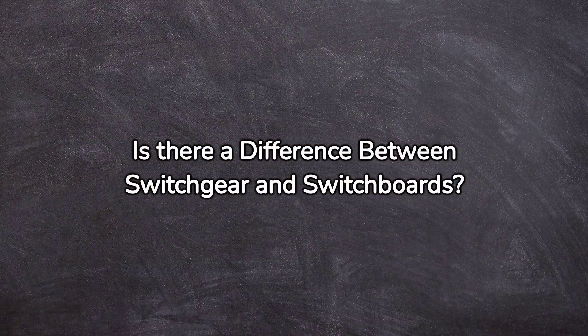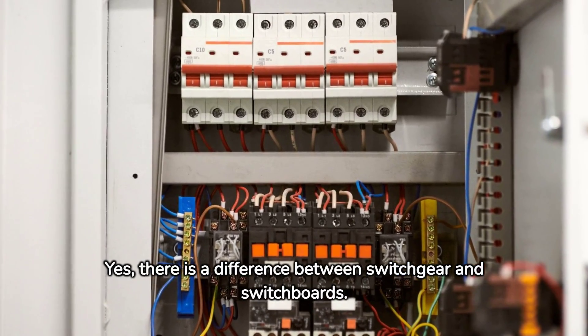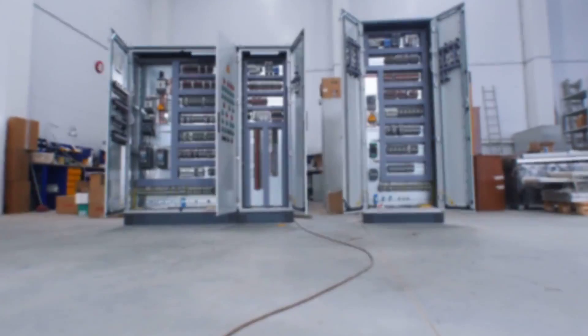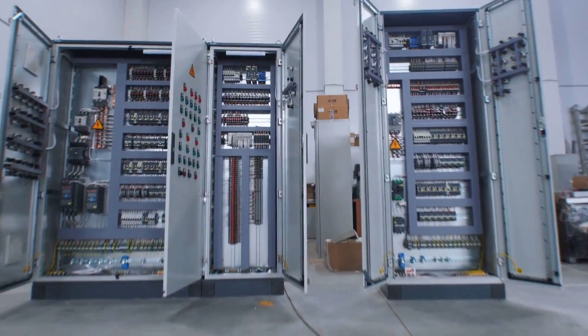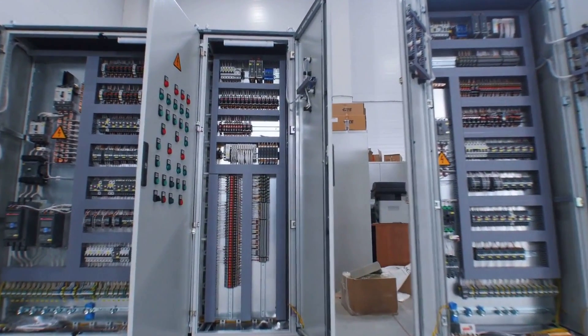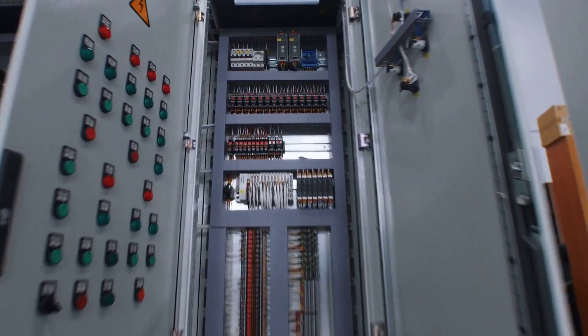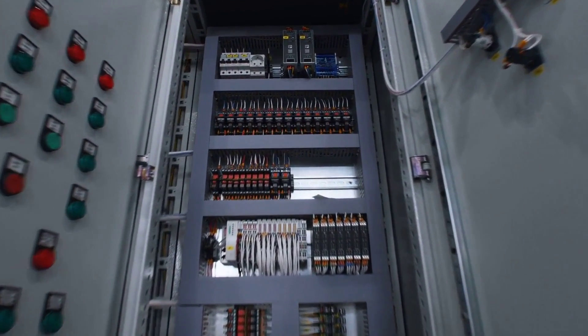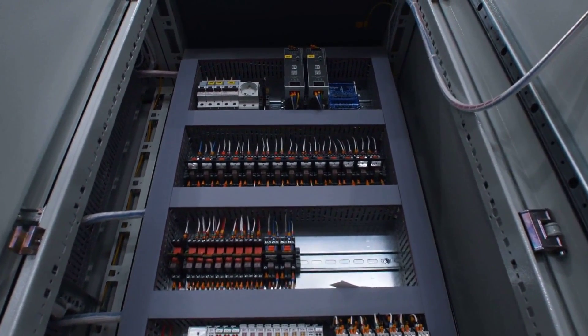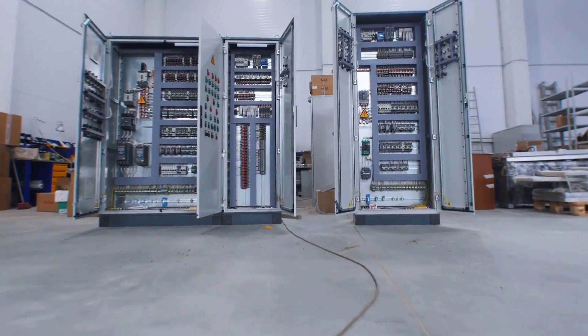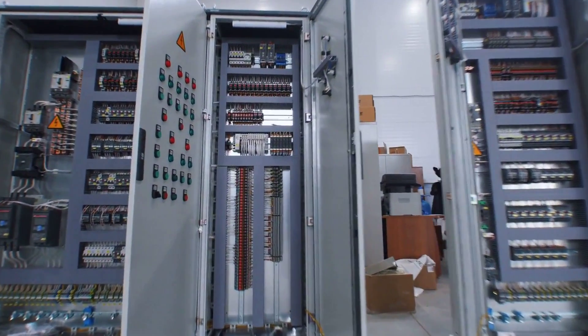Is there a difference between switchgear and switchboards? Yes, there is a difference. A switchboard is an assembly of switchgear with or without instruments, but the term does not apply to groups of local switches in final circuits. Switchgear refers to the electrical equipment used to control, protect, and isolate electrical power systems — it typically includes circuit breakers, fuses, switches, and relays, and is designed to operate at high voltages and currents. Switchboards, on the other hand, are typically low voltage distribution boards used to distribute power to various electrical loads within a building or facility.